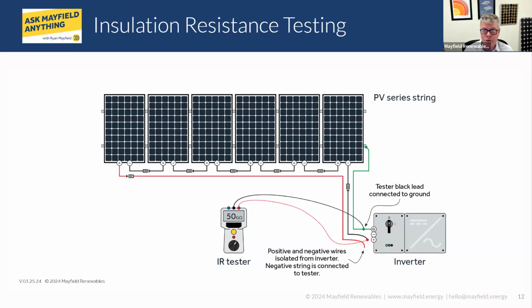If we have current that is getting in contact with the ground, with the racking system or the equipment grounding conductor, the meter will return a very low resistance value, maybe only in the kilo ohms. The meter, as you're seeing on the screen, is registering giga ohms right there in the center. That represents a very, very high resistance, which is exactly what we want.